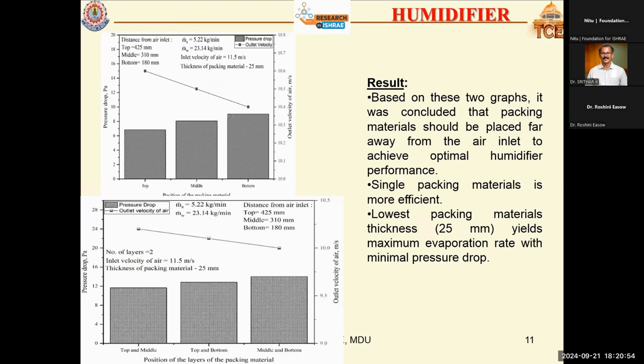The top graph shows when the packing material is fixed at the top side, fixed at the middle, and placed at the bottom. Similarly, the packing material is fixed at top and middle, top and bottom, and middle and bottom. We have compared the results mainly based on the pressure drop as well as the outlet velocity, because this moist air has to go to the dehumidifier with at least a somewhat higher velocity. So we have to choose the case with the highest air velocity and the lowest pressure drop.